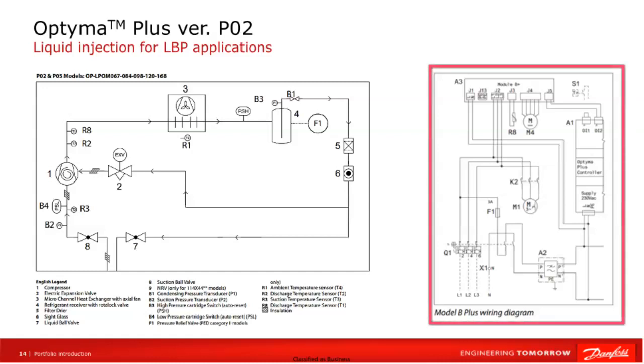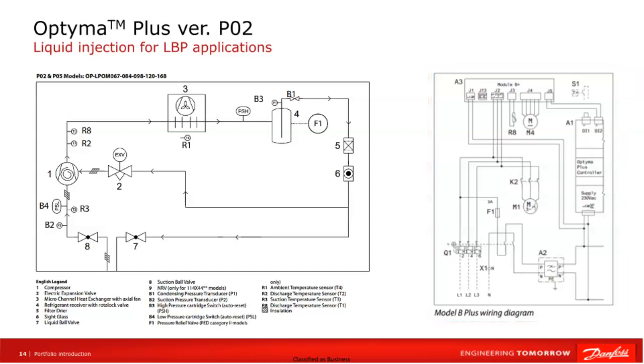On the right side of the slide, there is a part of the electrical diagram where we highlight an additional module that allows for the regulation of liquid injection. This module also monitors the discharge temperature, monitors the phase sequence, and checks the presence of voltage. These functions are crucial for the efficiency and safety of Optyma Plus unit in the P02 version.